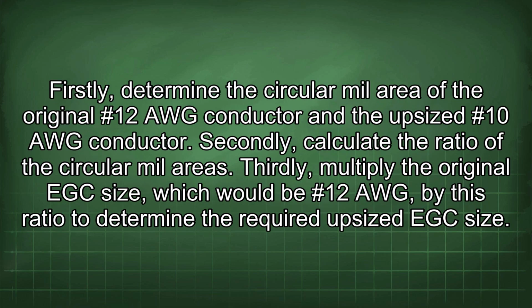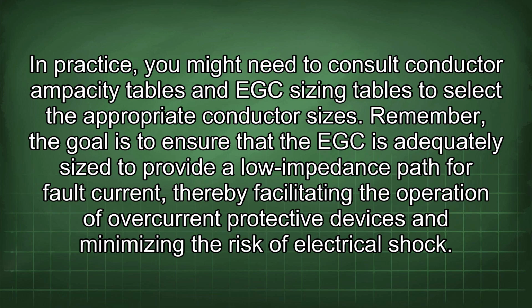Firstly, determine the circular mil area of the original #12 AWG conductor and the upsized #10 AWG conductor. Secondly, calculate the ratio of the circular mil areas. Thirdly, multiply the original EGC size, which would be #12 AWG, by this ratio to determine the required upsized EGC size. In practice, you might need to consult conductor ampacity tables and EGC sizing tables to select the appropriate conductor sizes. Remember, the goal is to ensure that the EGC is adequately sized to provide a low impedance path for fault current, thereby facilitating the operation of overcurrent protective devices and minimizing the risk of electrical shock.